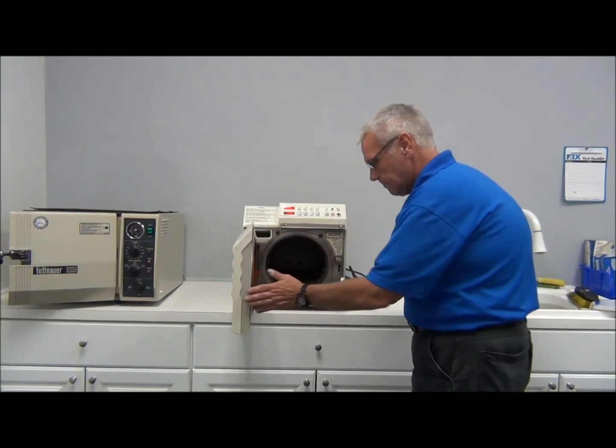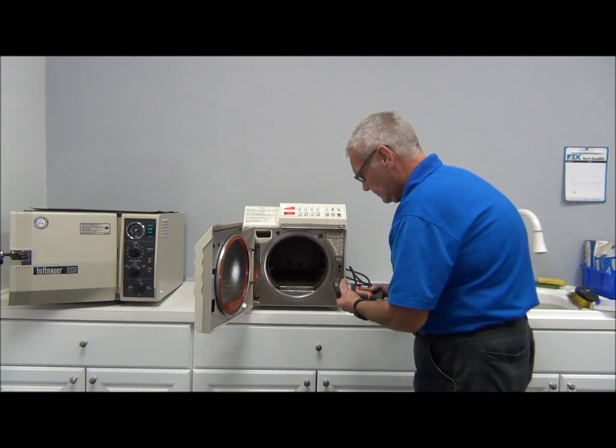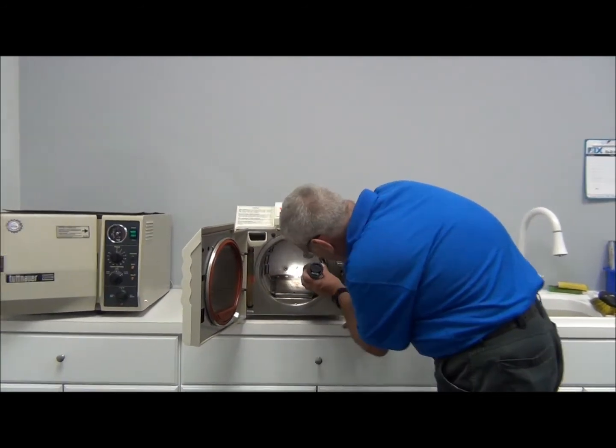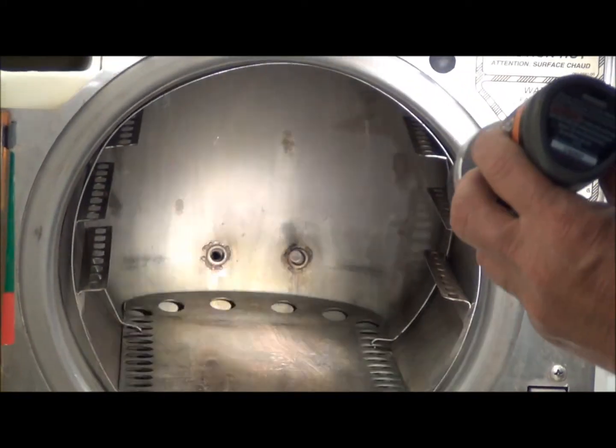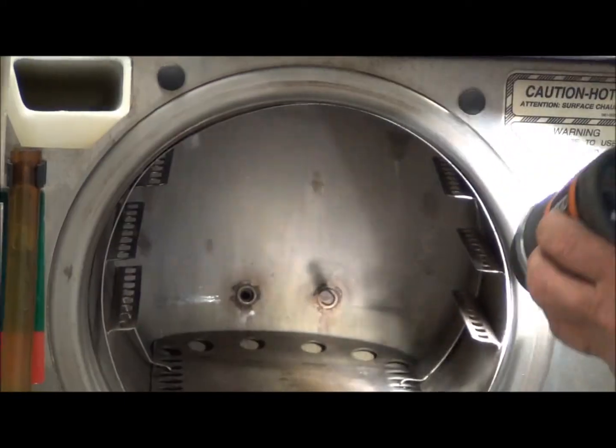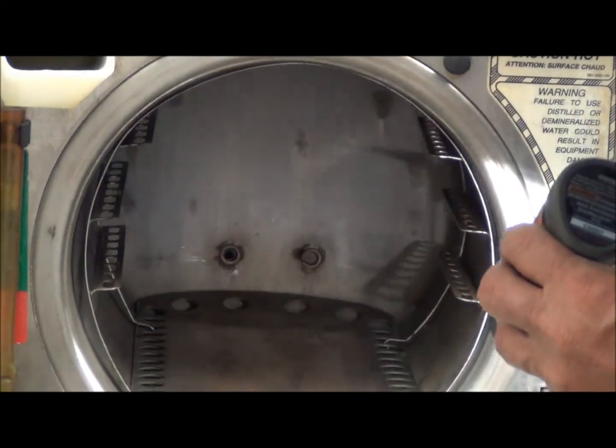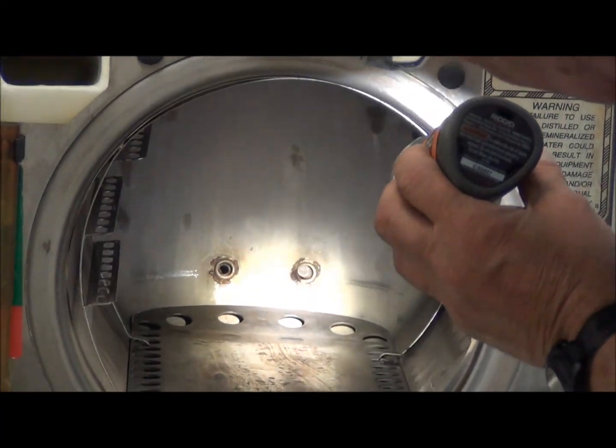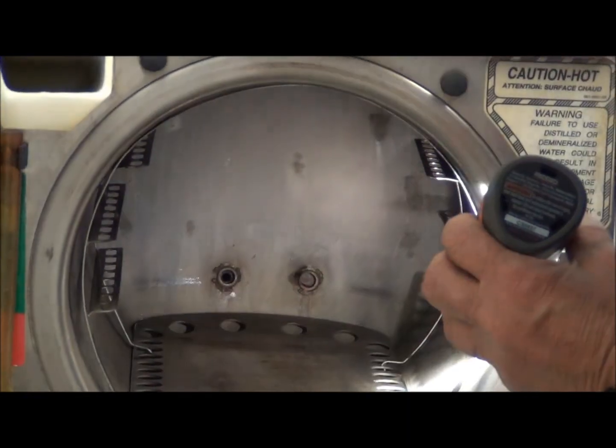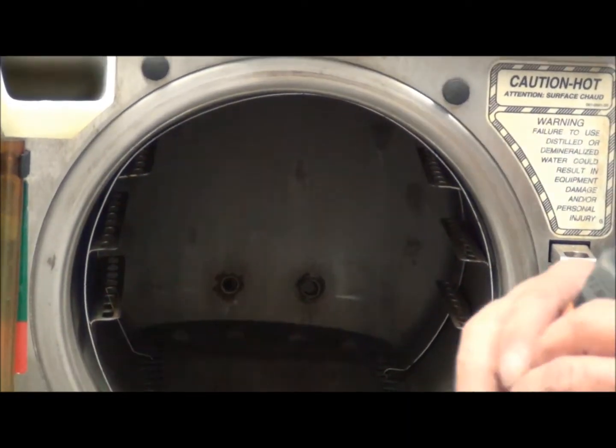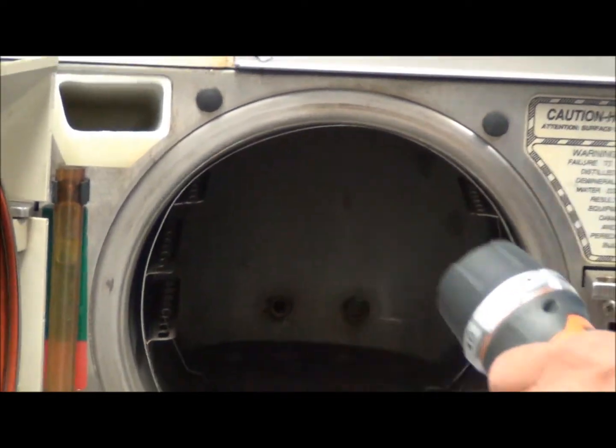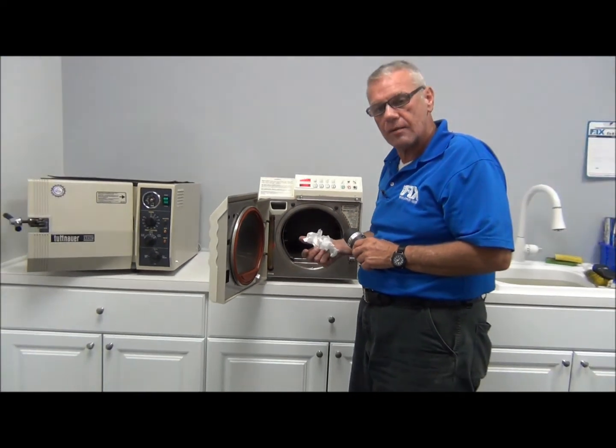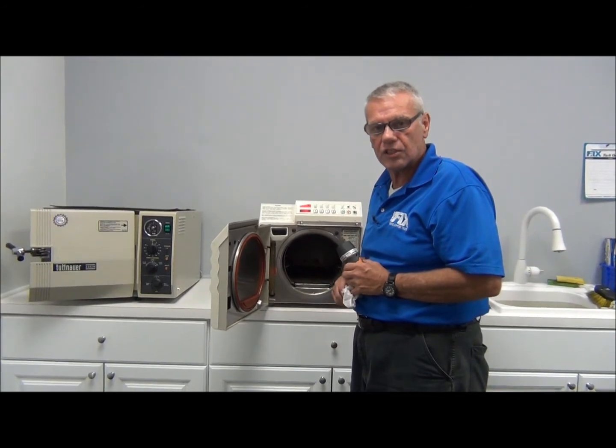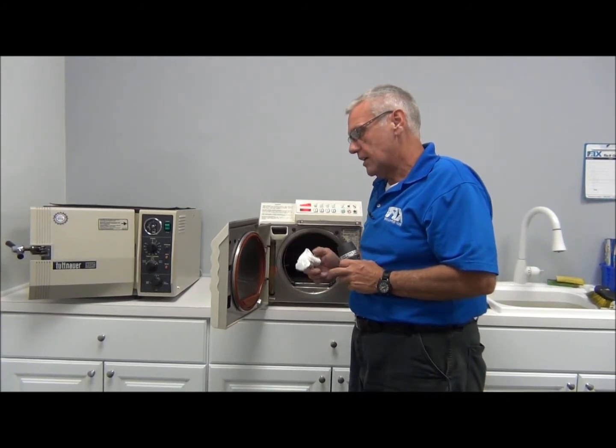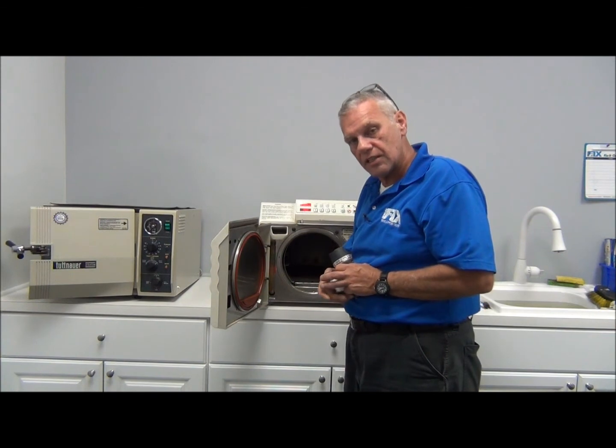Take your flashlight and ensure that you're not touching the temperature probe and that you're completely covering the water level sensor. Ladies and gentlemen, if you insert a tray back in here, or if this machine is overloaded and anything touches that temperature probe where the light's concentrated, it will read the temperature of the platform in the tray instead of the chamber, and will fail the cycle every time, ladies and gentlemen. Again, on any PM, always check your doctor's spore tests.